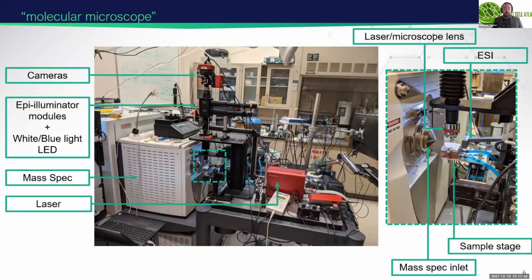This is a picture of the actual source. We have two cameras and two light sources — bright field and fluorescence — attached to a mass spec with a high mass resolving Orbitrap detector. You can see the laser box, and in the zoomed-in picture, you can actually see the sample stage with intercepting ESI and the MS inlet. We also have a dual reflective objective, which allows us to focus the laser and also focus the image.